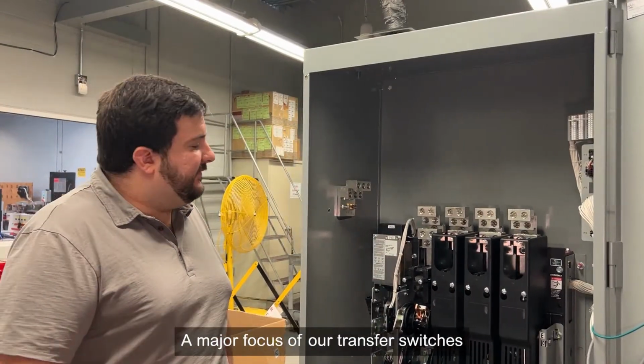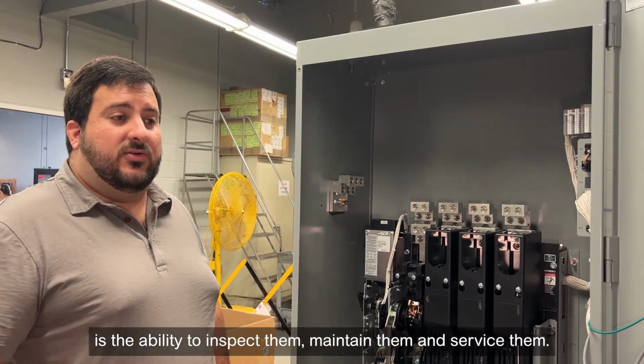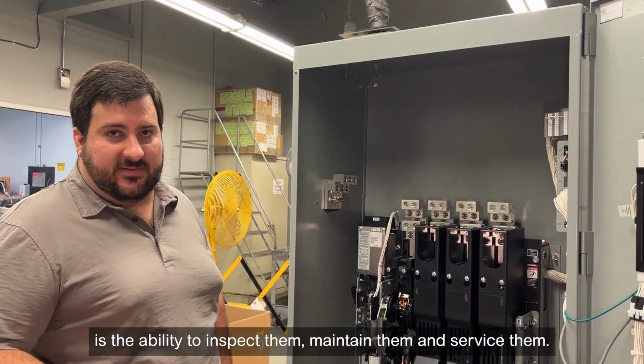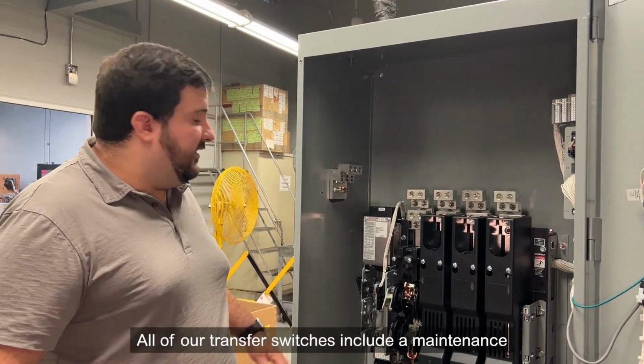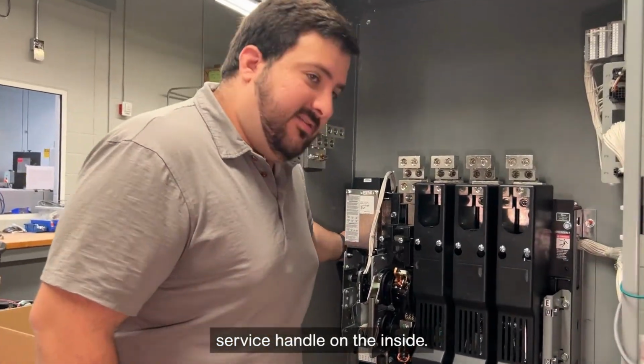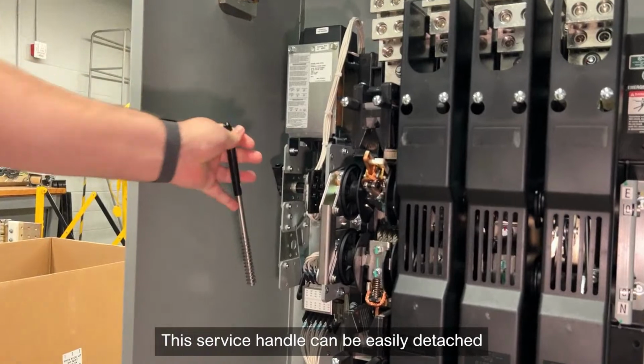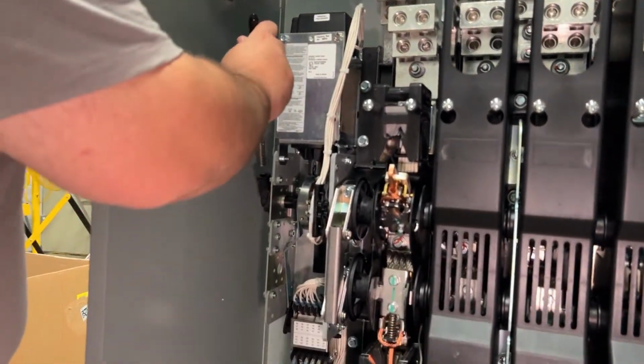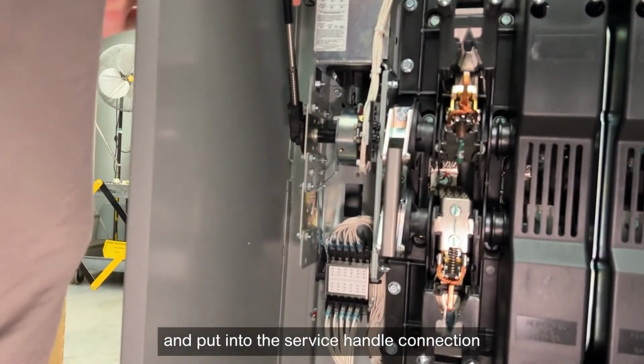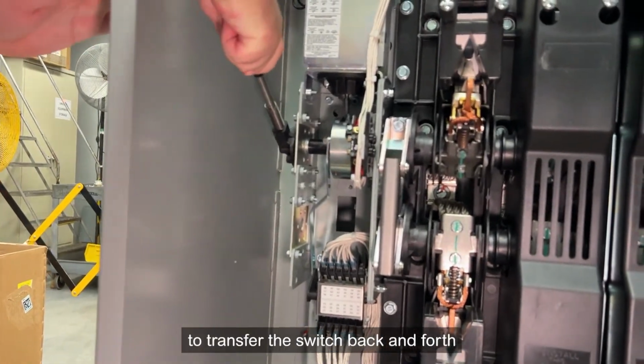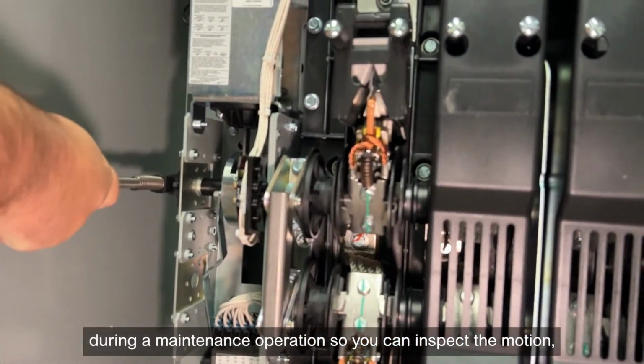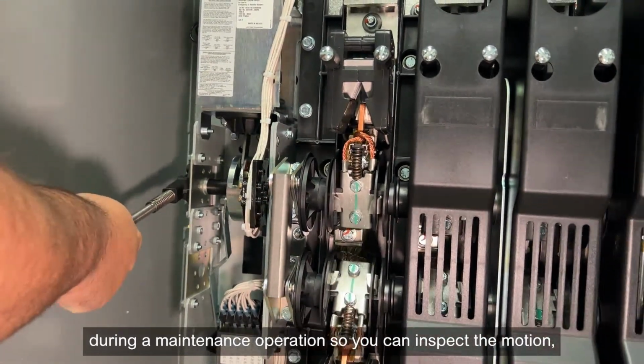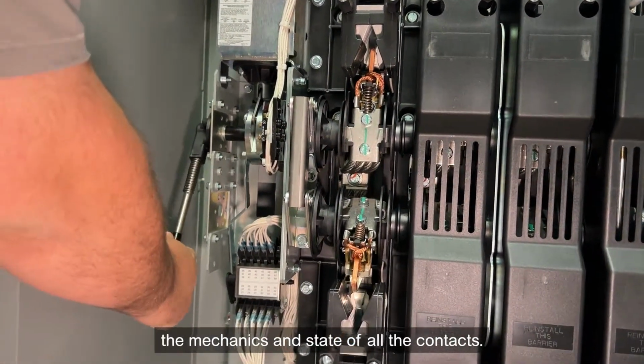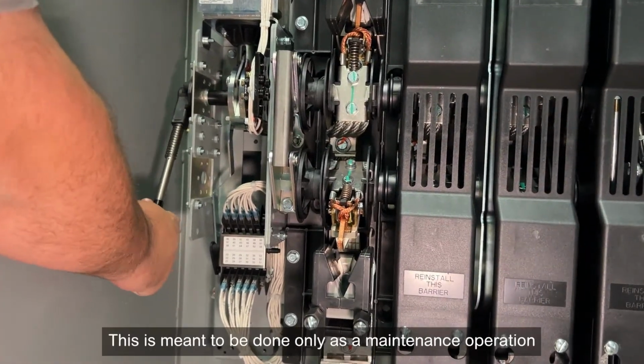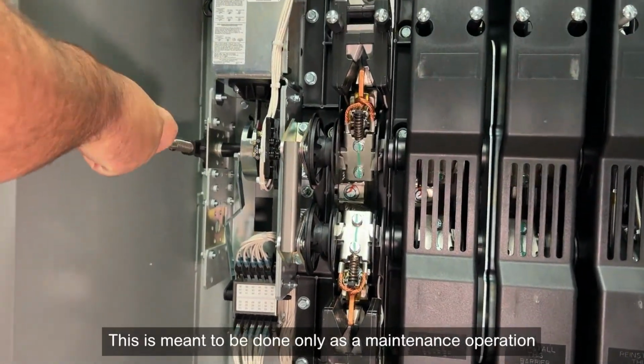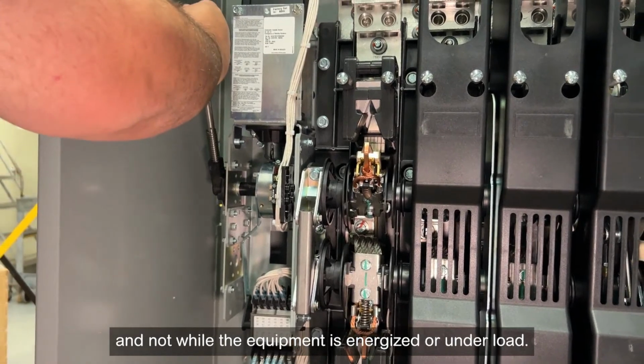A major focus of our transfer switches is the ability to inspect them, maintain them, and service them. All of our transfer switches include a maintenance service handle on the inside. This service handle can be easily detached and put into the service handle connection to transfer the switch back and forth during a maintenance operation, so you can inspect the motion, the mechanics, and state of all the contacts. This is meant to be done only as a maintenance operation and not while the equipment is energized or under load.